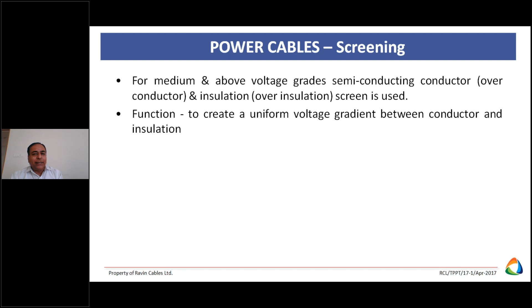Now these are the basics. Once you are going for your selection of the cable, these properties come into the picture. These considerations are required. We already discussed screening in medium voltage cables. Semiconductors are required to make a uniform potential gradient between conductor and insulation. We also discussed the metallic part. Why is the metallic part required over the insulation? To earth electrical charges. Whatever unwanted charges are available on the insulation surface should be drained out. Again, this gives a passage to earth fault current.